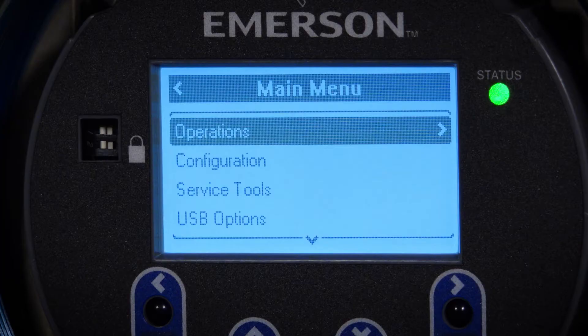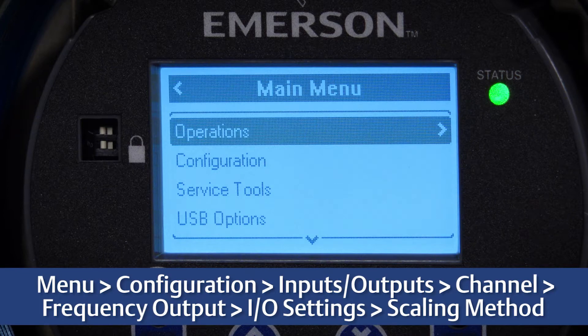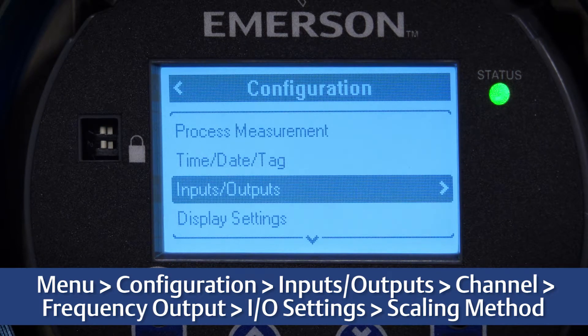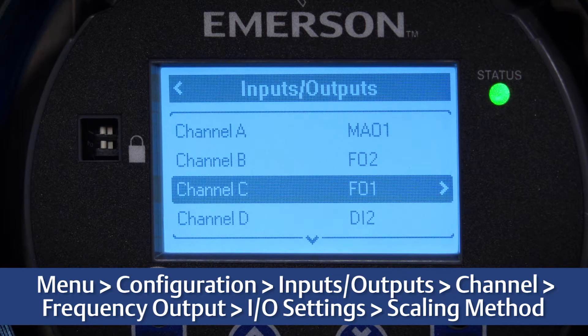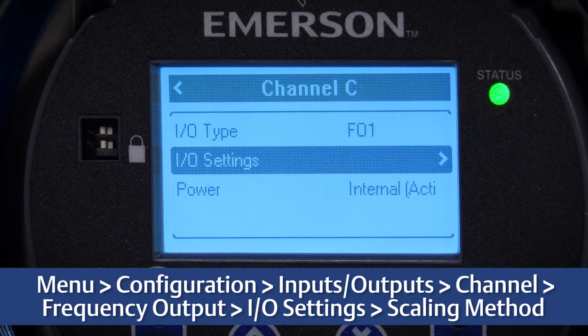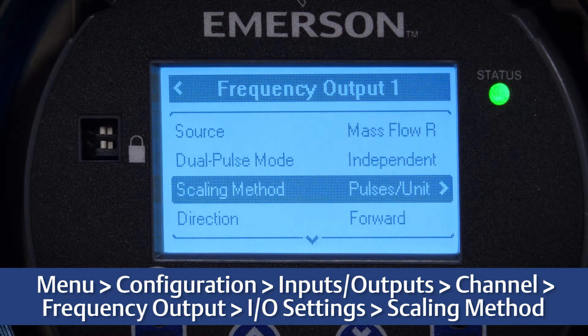Scale the frequency output to provide the data in the form required by the device that is receiving the transmitter frequency. This can be completed by using the display and selecting Menu > Configuration > Inputs/Outputs > Channel > Frequency Output > IO Settings > Scaling Method.